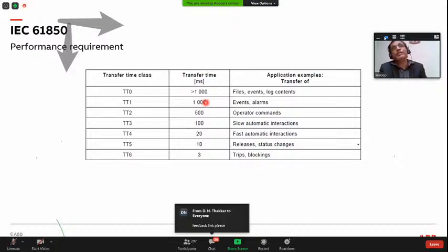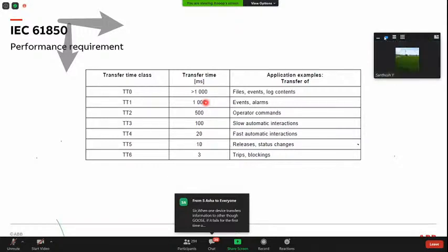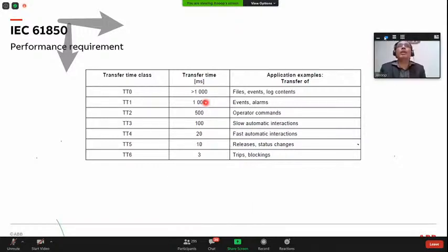Then I brought in this standard called IEC 61850. Why did it come into the picture? So that the utility can mix and match different manufacturer devices in their substation, ABB, GE, Siemens, everything. The main aspect was that they should talk the same language. Interoperability is what I was mentioning. To achieve interoperability, we defined a language using logical node, data object, and common data class. I showed you the modeling using STMP, the temperature supervision function, and how the addressing is done there.